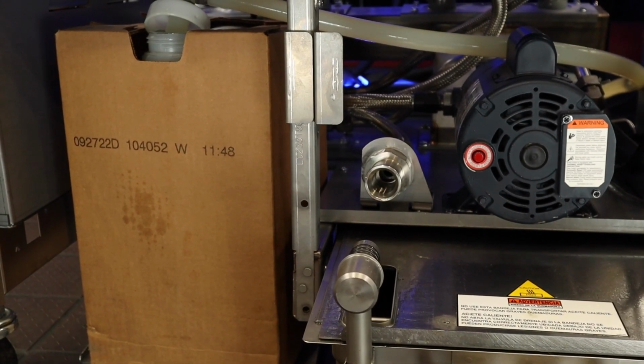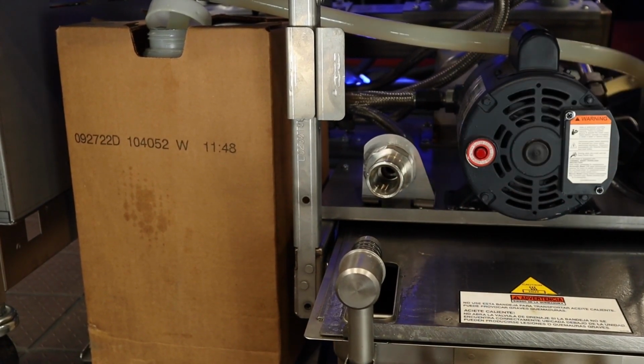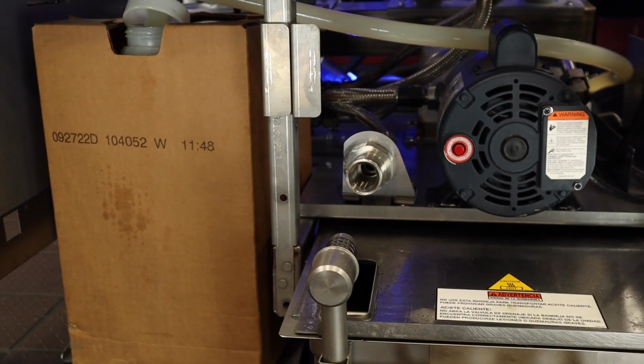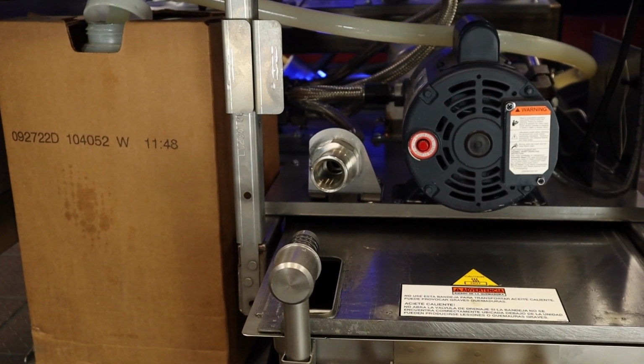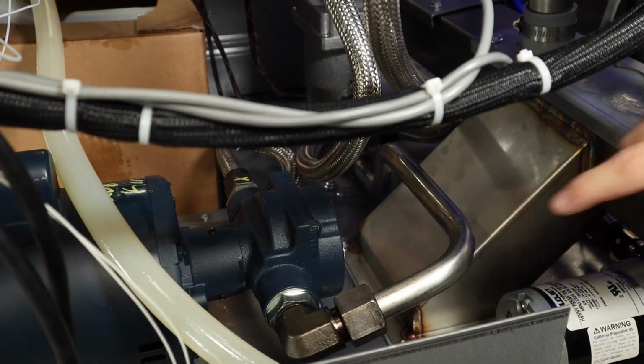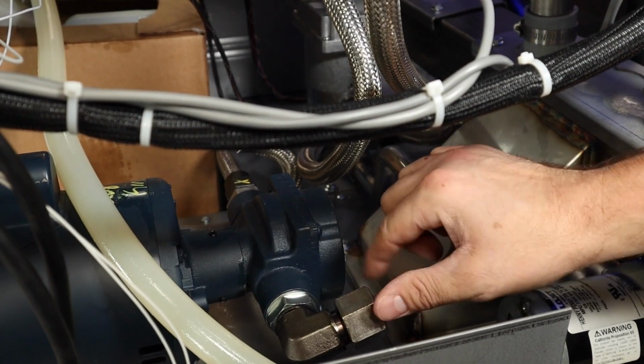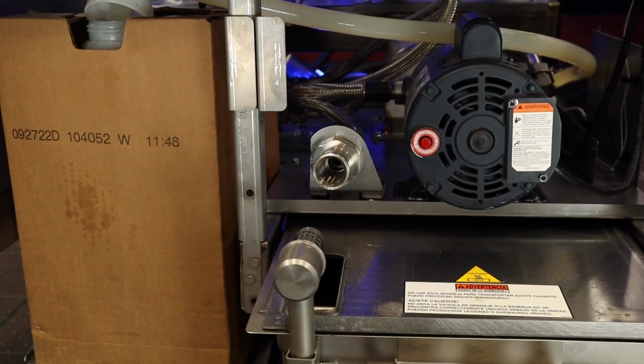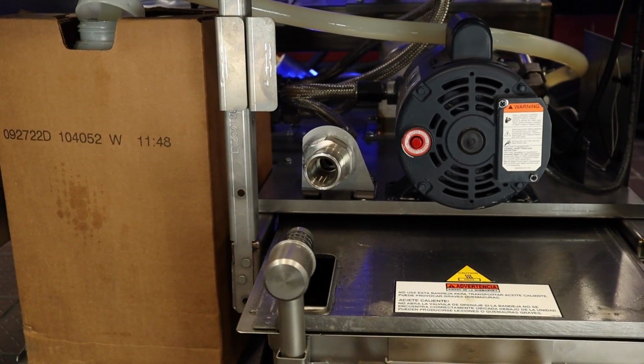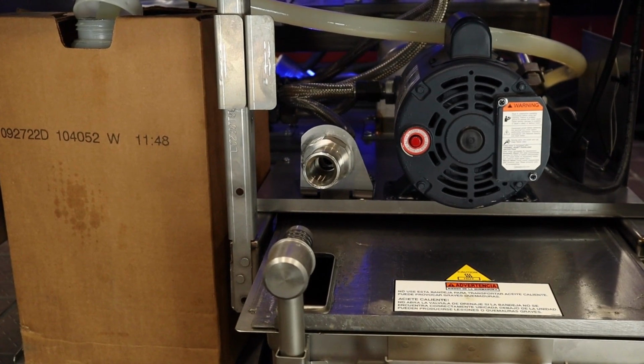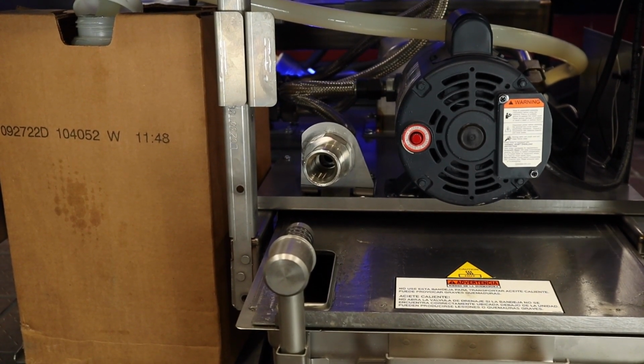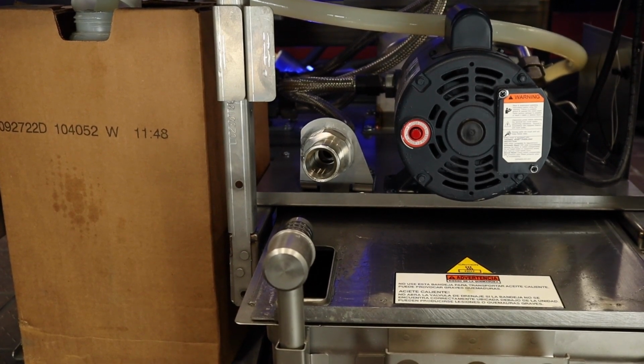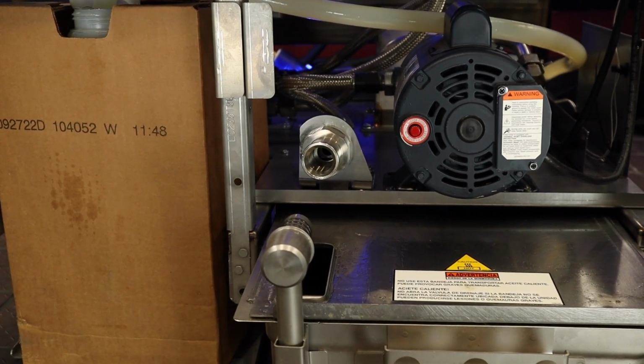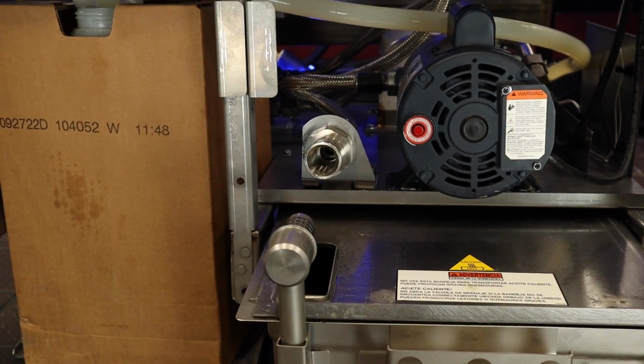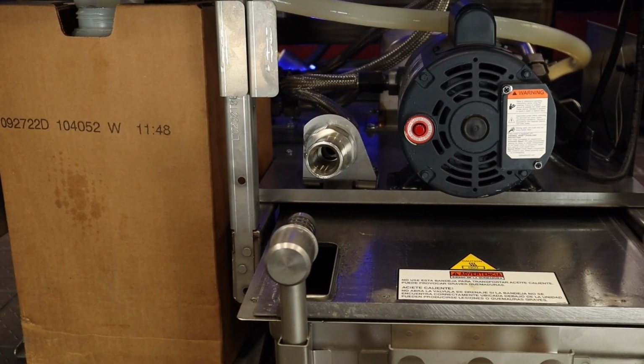On the flip side of that, what if I don't have suction here at all? Well, I want to know if the problem is in my pump or if I have a clogged check valve or something like that. So I want to start by taking off the outgoing line of my filter pump and then coming back up here and checking for suction. If I have suction, then I know my pump is good and the problem is past the pump, like maybe a check valve. If I take that line off though, and I still don't have suction, then I know the suction issue is within my pump and I might have a bad pump or bad rollers, leaking O-ring, etc.